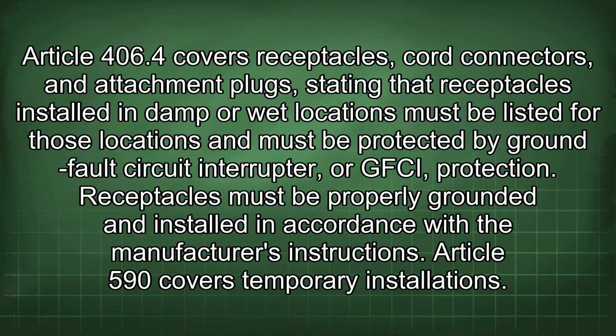Article 406.4 covers receptacles, cord connectors, and attachment plugs, stating that receptacles installed in damp or wet locations must be listed for those locations and must be protected by ground fault circuit interrupter, or GFCI, protection. Receptacles must be properly grounded and installed in accordance with the manufacturer's instructions.